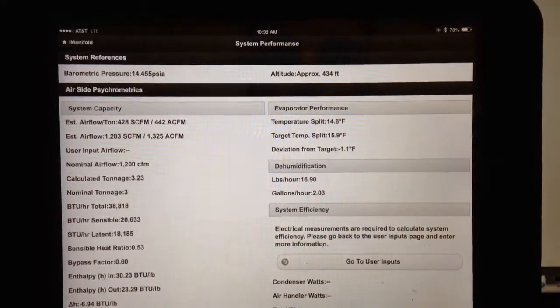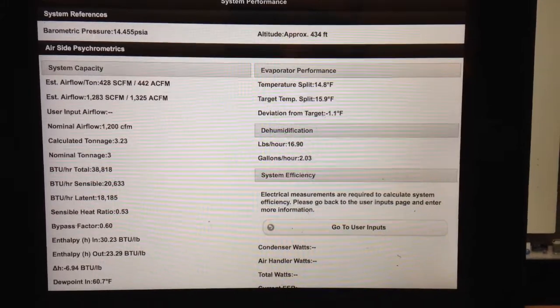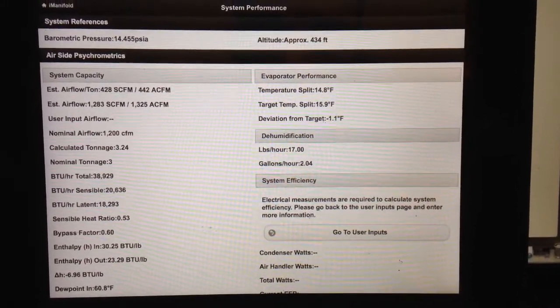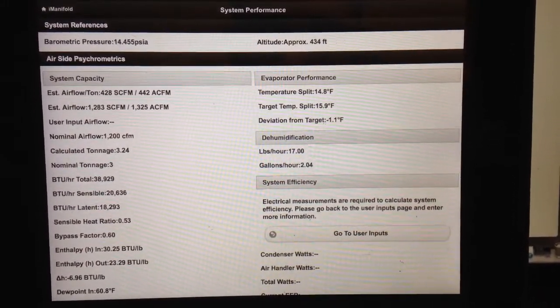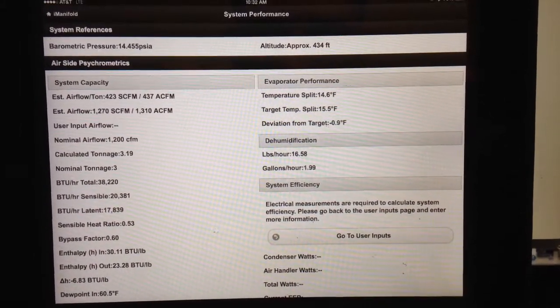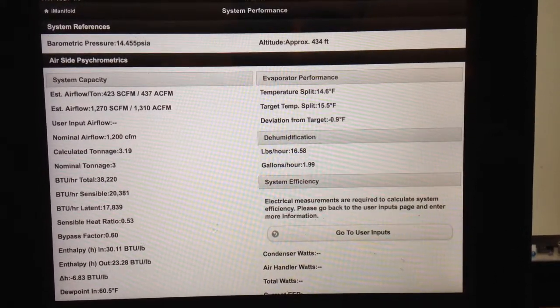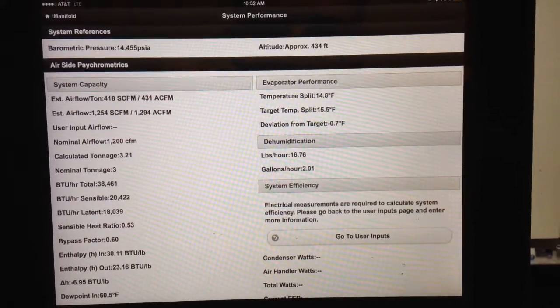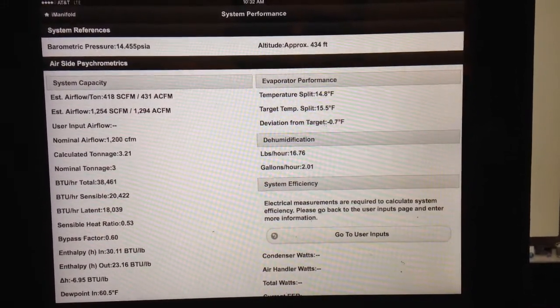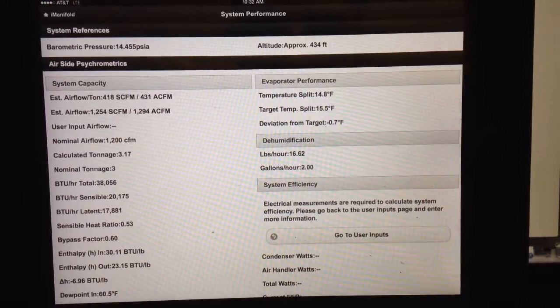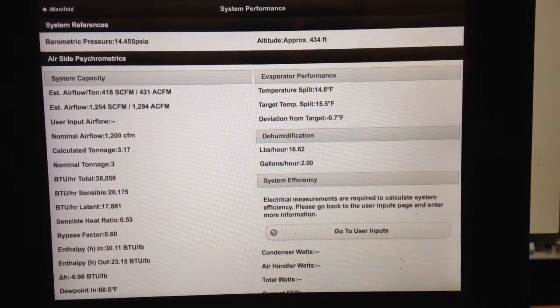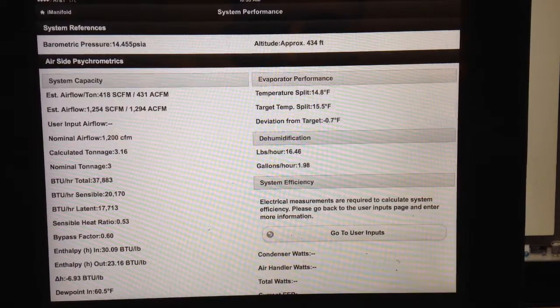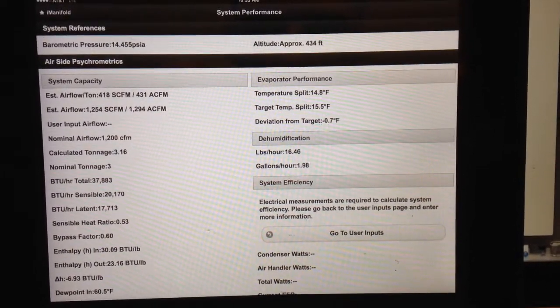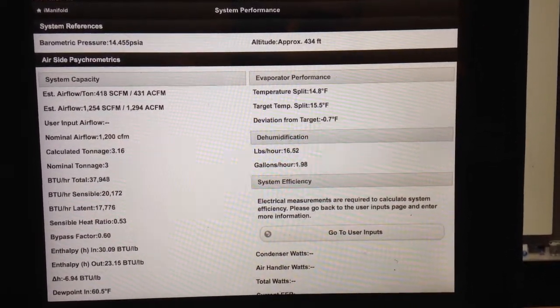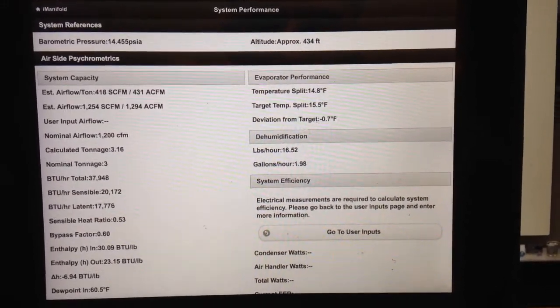Go back to system performance, see how that has changed. Not a whole lot. My target temperature split has gone up a little bit to almost 16. Still lagging behind by about 1 degree roughly. But the CFM has maintained its accuracy to the true 1200 nominal. Pretty decent, I'd say. Like I said, 13 years old.